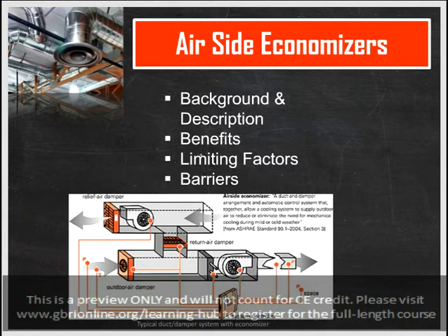And then finally, mechanical cooling mode. Economizer operation is disabled during warm weather when outdoor conditions exceed the high limit shutoff setting. Minimum outdoor air for ventilation, determined by standard 62.1 or the local building code, mixes with return air. The mixed air is then mechanically cooled as needed to maintain the supply air temperature at set point.